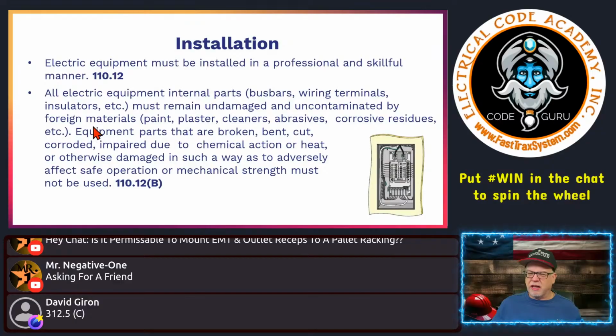All right. All electrical equipment, internal parts, bus bars, wiring, terminals, insulators, etc., must remain undamaged and uncontaminated by foreign materials. Paint, plaster, cleaner, abrasive, corrosive residues, etc. How many times have you guys been in, and I was real anal about this, that I made sure that when I put my panels in a wall, that I put the cover, I cut out, usually they have a little cutout, I cut it out and I would put it in there because, you know what, I did not rely on the fact that every painter or plasterer or sheetrocker or mudder, there was a video going around on I think it was Instagram, where the guy threw the mud in the box.